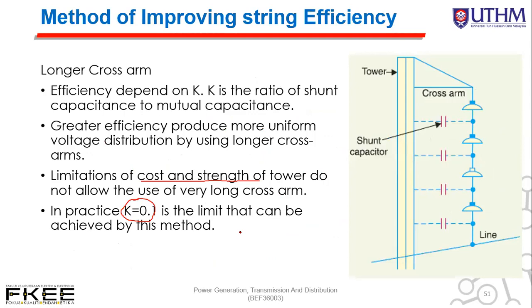The method for improving string efficiency: first, use longer cross arms. String efficiency depends on K, where K = C1/C (ratio of shunt capacitance to mutual capacitance). Greater efficiency produces more uniform voltage distribution. Using longer cross arms reduces the shunt capacitance. However, the strength of the tower limits the use of very long cross arms. In practice, K = 0.1 is the limit achievable by this method.